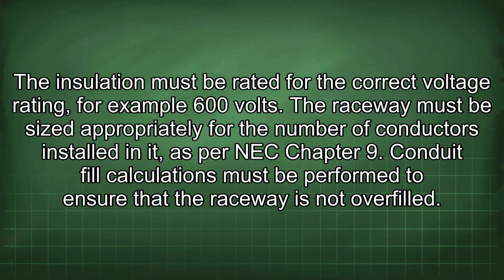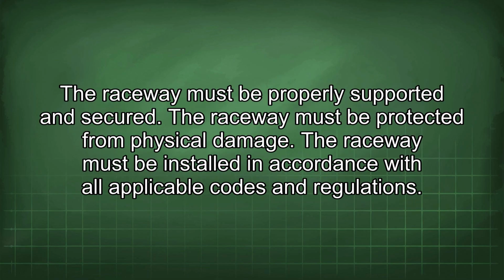The raceway must be sized appropriately for the number of conductors installed in it, as per NEC Chapter 9. Conduit fill calculations must be performed to ensure that the raceway is not overfilled. The raceway must be properly supported and secured. The raceway must be protected from physical damage. The raceway must be installed in accordance with all applicable codes and regulations.